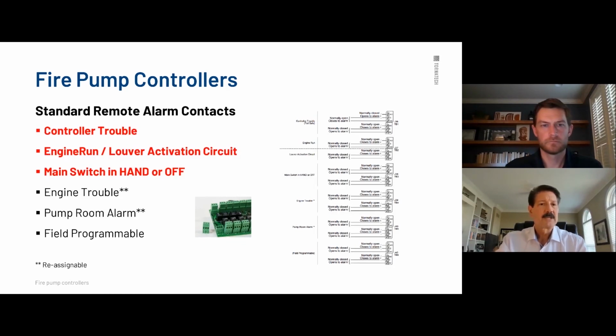Let's just look at remote standard. Again, standard remote alarm. Same thing. It's 8 amp, 250 volt, controller trouble, engine run, louver activation circuit. 8 amps is a lot, and your louver activation circuits typically aren't going to exceed 8 amps. And we want to know, is it hand or off? Because if it's in hand or off, you do not have fire protection. It's not an automatic. And then you have incremental extra remote alarms right here. We kind of covered those in the electric also. Pull apart terminals.